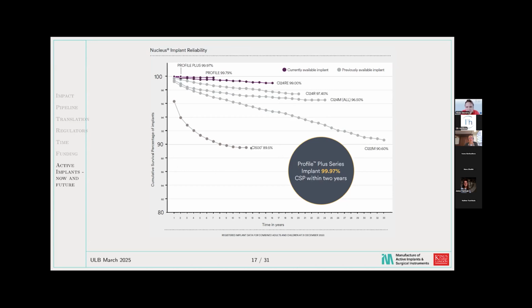where we also see the dramatic effect of an innovation that wasn't suitably or sufficiently tested for long-term reliability, because testing to see whether a device will succeed or fail after 5 years requires a very long period. And sometimes this is just not done sufficiently. So they retired this device early because its performance was below what would have been expected. We see, however, in the most recent devices, that every generation of the product increases its reliability, so that even over 30 to 50 years we're going to see very little failure. The target is a device for life, absolutely, literally.